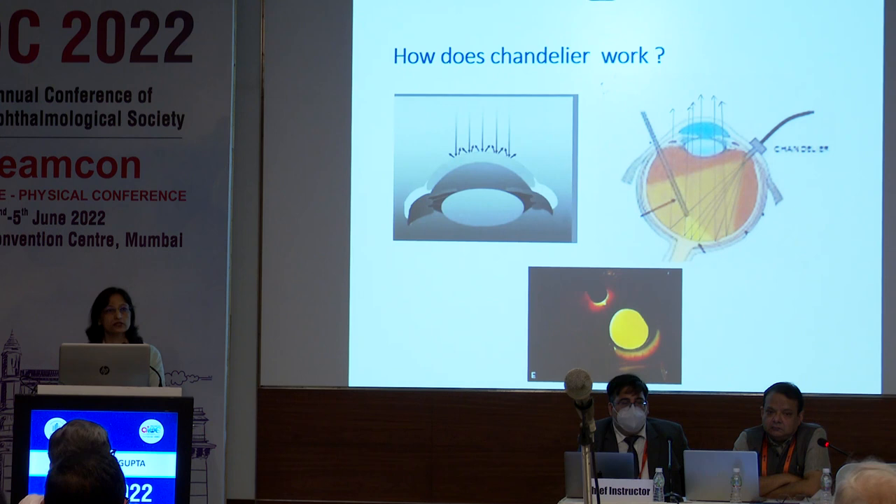How does the chandelier system work? When you have a corneal opacity, light from the microscope falls on the cornea and gets scattered back, leading to poor red glow. But with the wide angle illumination of the chandelier illuminator, when the light falls on the retina it gets reflected back. This bypasses the corneal opacity, giving you a very good red glow, good intraoperative visibility, and increased depth perception.